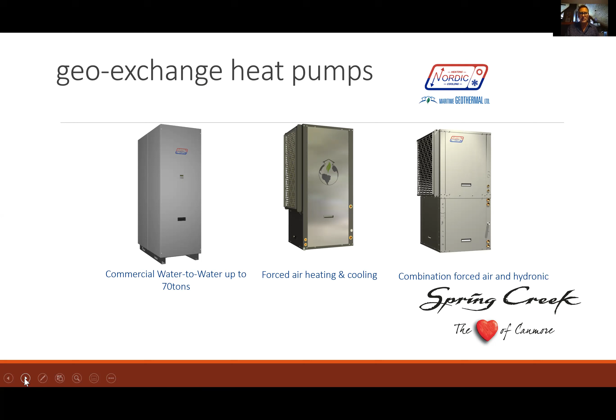Common loop field designs - the most common is probably the vertical closed loop. Generally you drill down 200 to 400 feet. For my apartment building we did 50 boreholes. Very costly, and this is where people say GeoExchange is costly. For a single family home it's usually just a couple of boreholes, but for my 26-unit building we had to do 50.